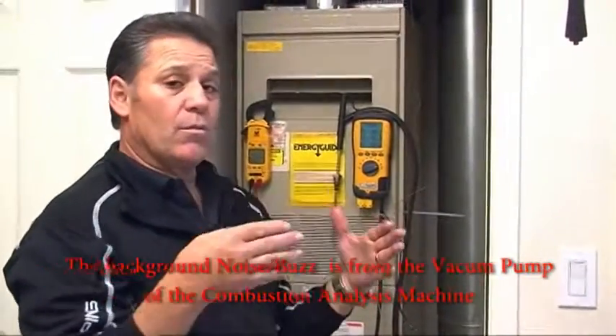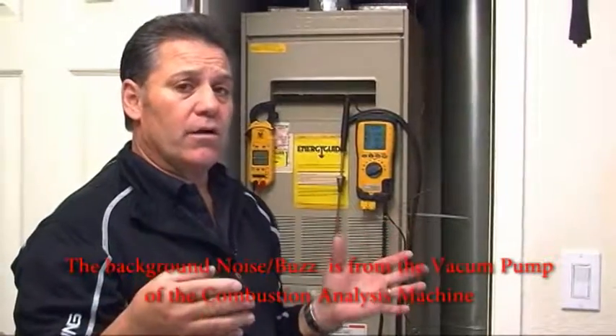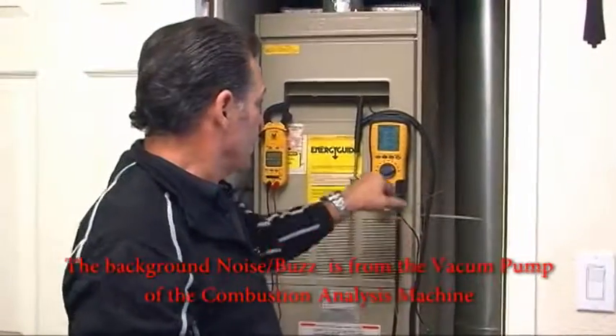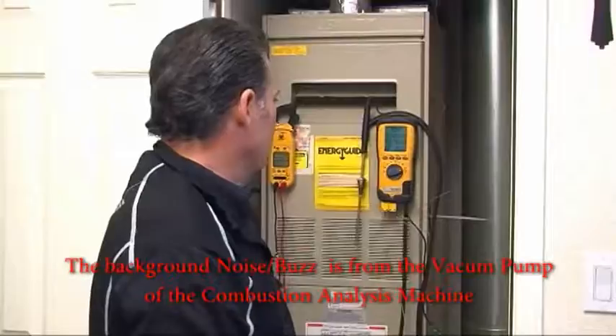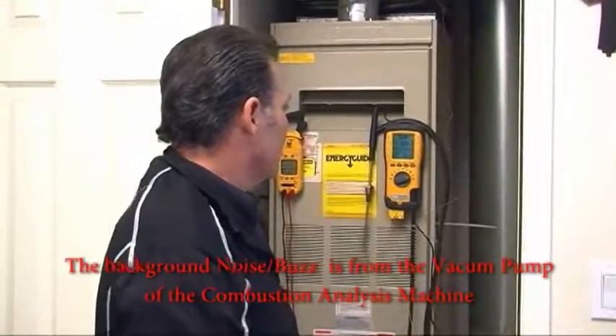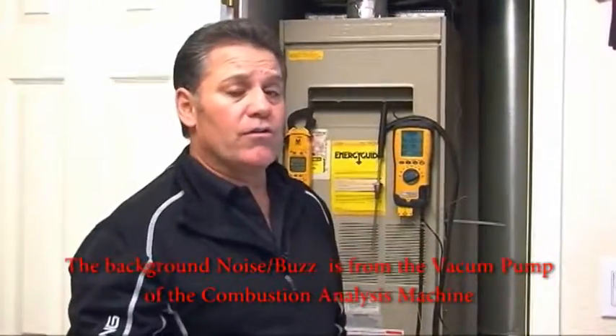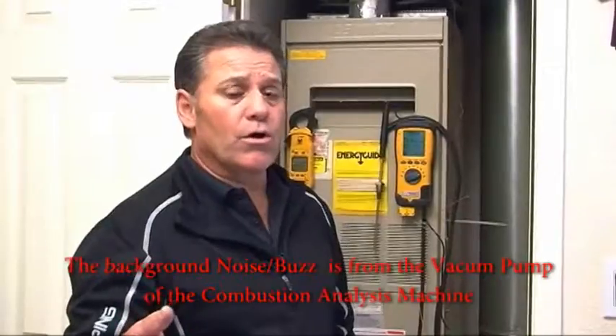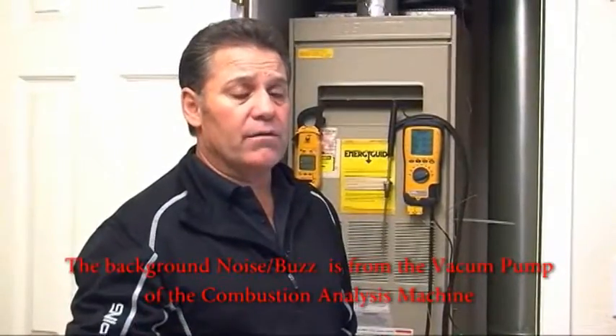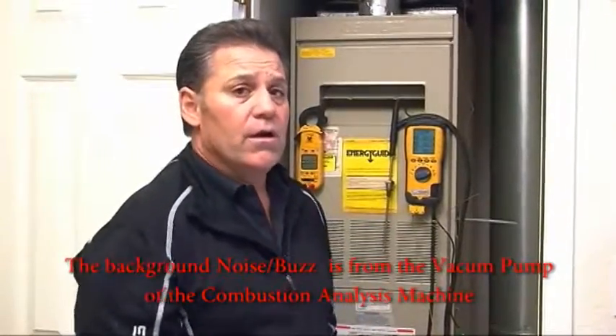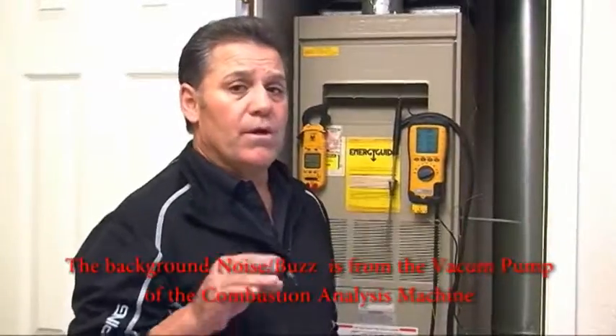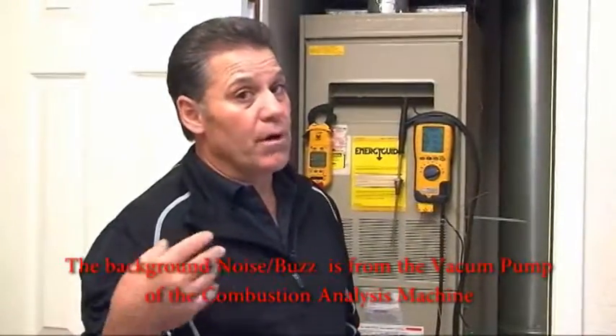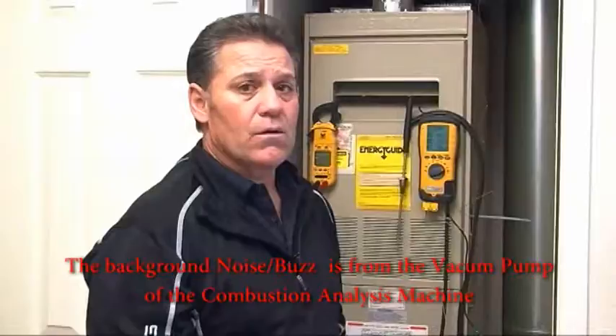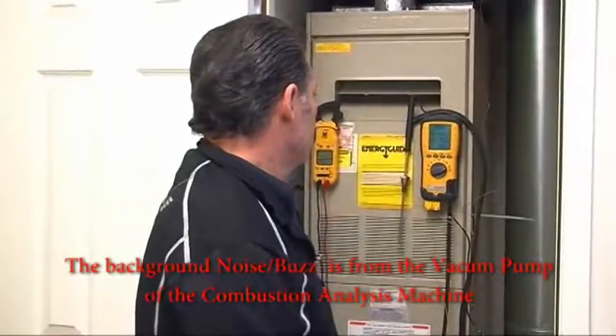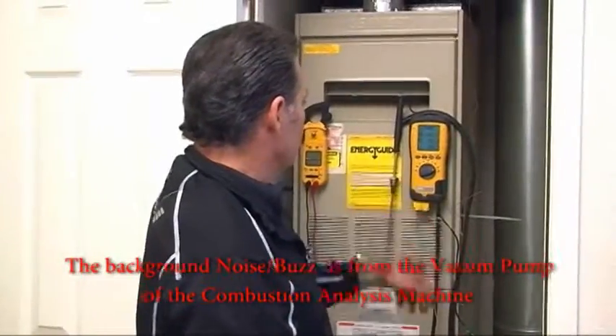And we want to be somewhere between 70 and 100 degrees on our temperature rise or our delta T. Right now we're at 74, 76. This is how you know whether you need to turn up the blower motor or leave it where it's at, or possibly turn it down. You don't want to be below 70 and you don't want to be above 100. Looks like it's settled out.